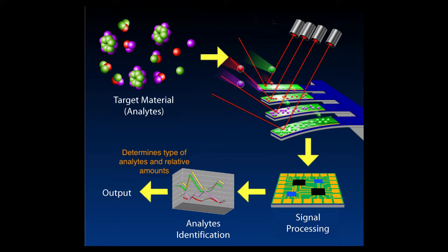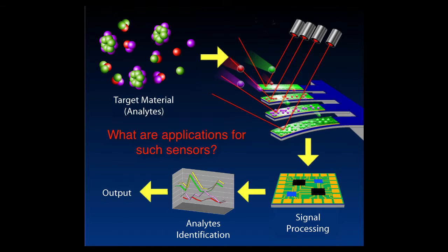To determine the type and relative amount of each analyte, the CSA depends on the reactions at the surface of the cantilevers, the amount of Z displacement, and thus changes in the angles deflected off the cantilever surfaces. See if you can come up with some applications for this type of MEMS sensor.